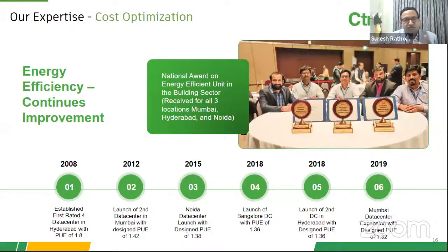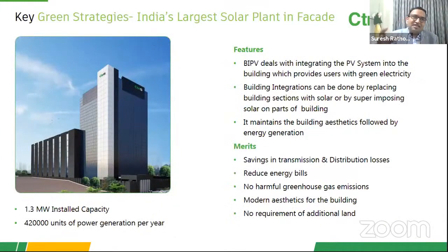If you see the first data center in 2008, the design PUE is 1.8. And the last one, which we designed in 2019, is 1.32. Now, these are all designed PUEs. Obviously, the data centers are operated at slightly higher PUEs than the design, because you don't get the ideal IT load all the time. You have to work with a disparate IT load from all the customers, some from 4 kilowatt to 30 kilowatt. Another great initiative follows.